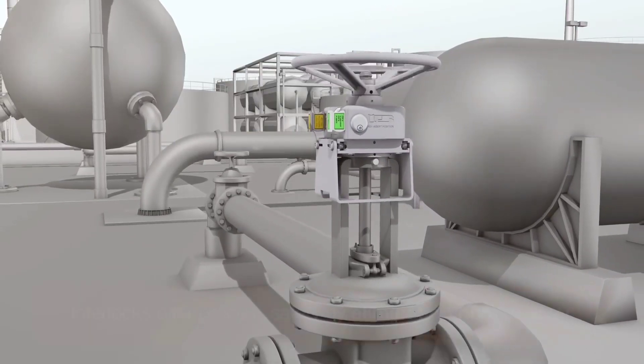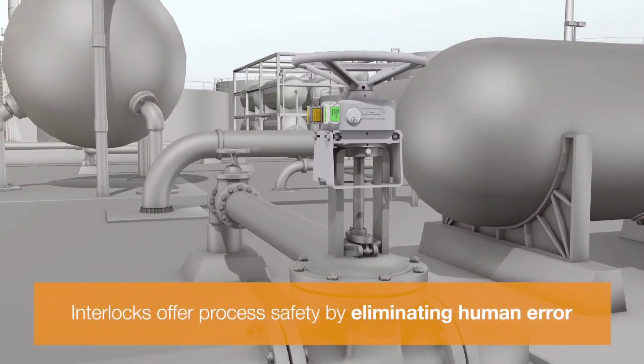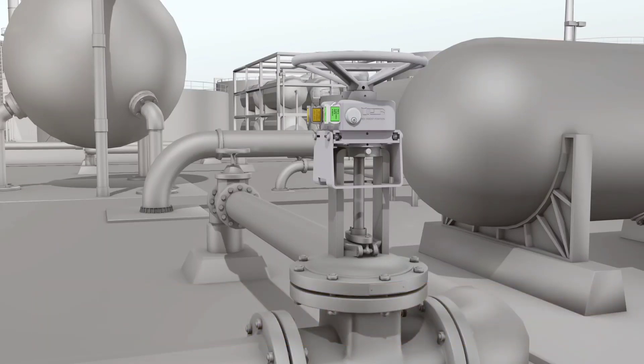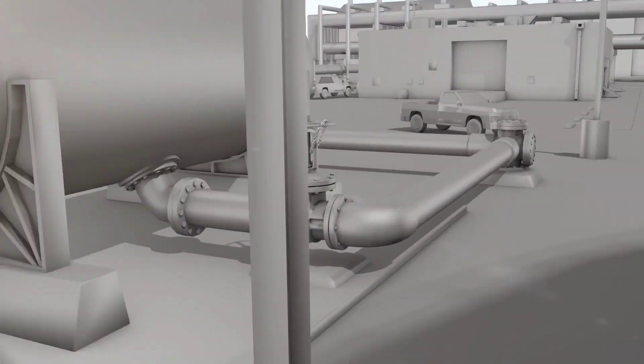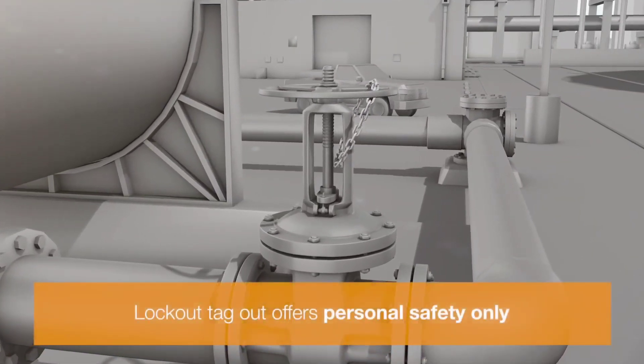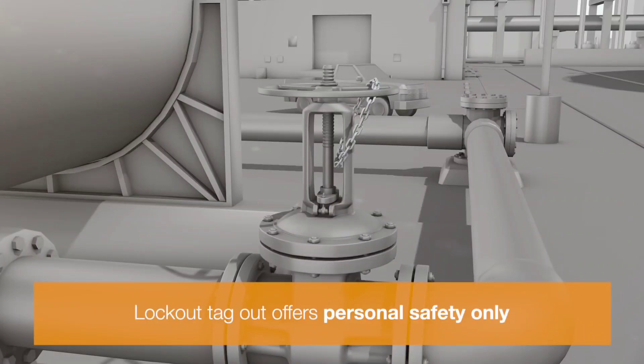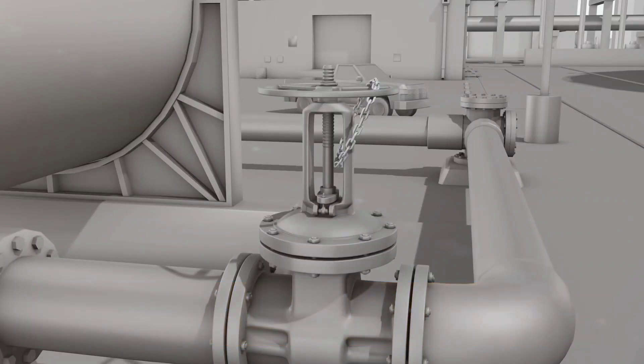Valve interlocks are permanently installed on a valve. They improve process safety by preventing incorrect valve operation. Lockout tagout products temporarily lock out valves. They only offer personal safety and should not be used for process safety purposes.